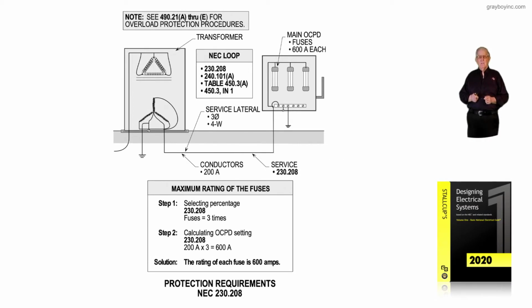Now we're reviewing protection requirements in accordance with 230.208, but instead of using circuit breakers for protection, we're using fuses, and the systems are rated over 1,000 volts. Now let's look at that NEC loop. We still start with 230.208, but we're going to 240.101(A), as in apple. We're reviewing Table 450.3(A) for protecting transformers, and we're looking at 450.3 and the informational note.